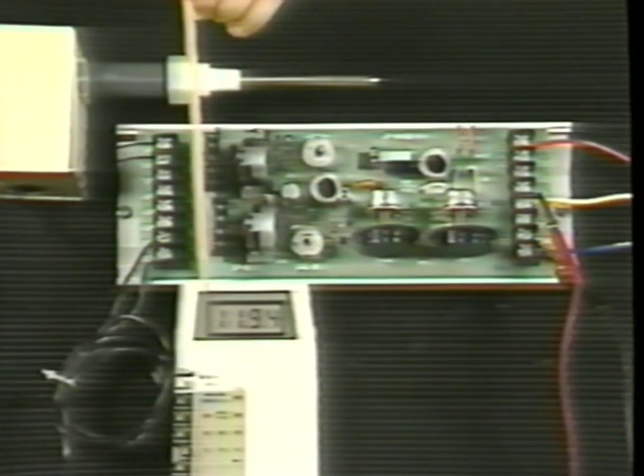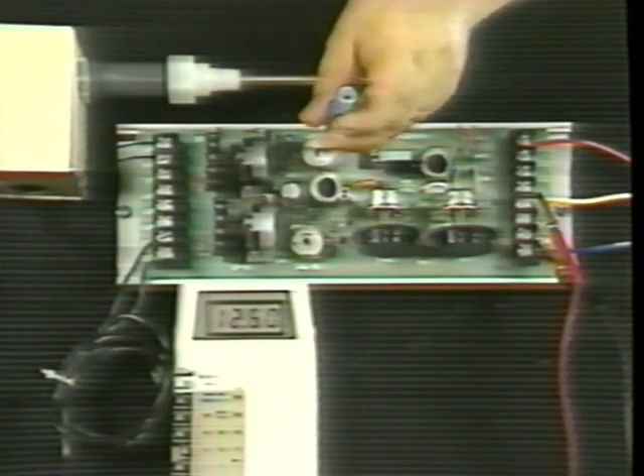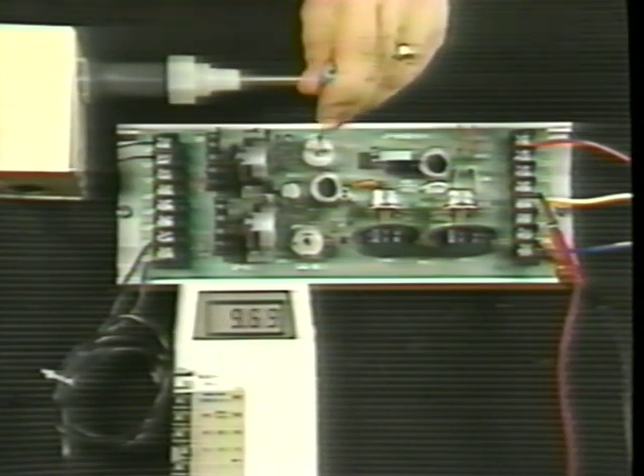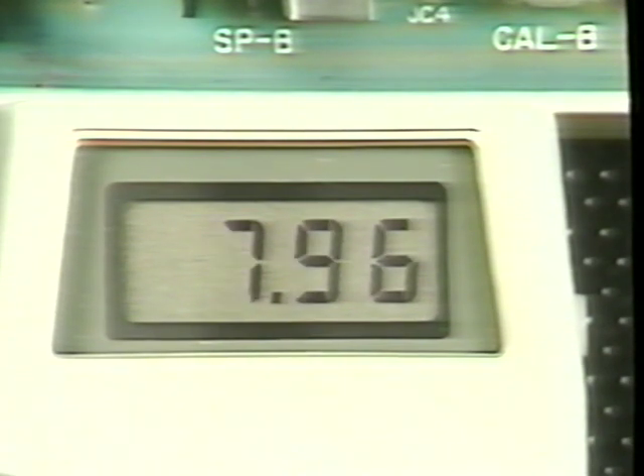Standard calibration voltage is 7.5, and in fact the CP8102 is factory calibrated. In this case, the voltage is far from 7.5, so it will be necessary to adjust the calibration pot. Turn the pot clockwise or counterclockwise until the desired voltage is attained. If input A is the only sensor being used, we would now restore set point A to the desired value, and that completes our calibration.